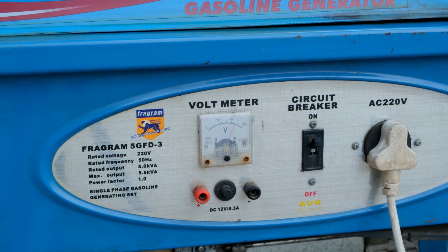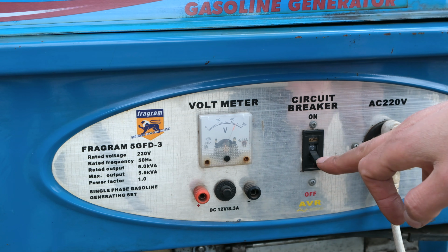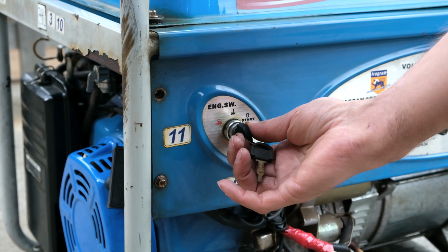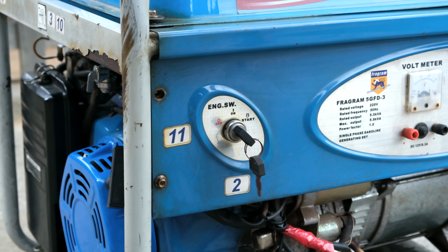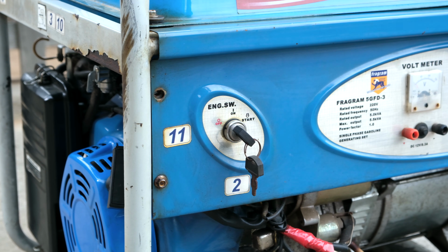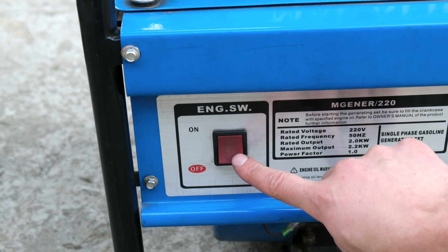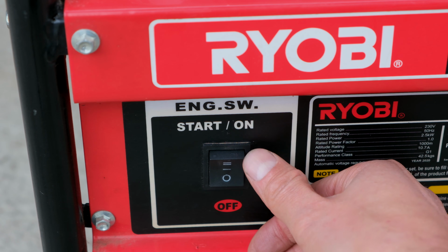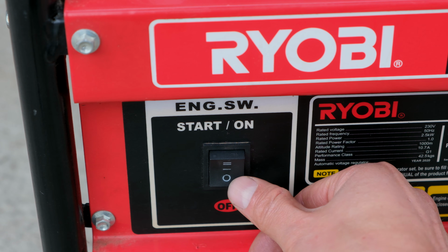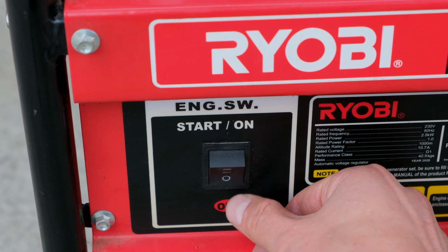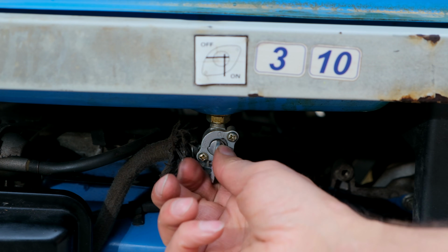To stop the generator, please do as follows. Switch off all your appliances. Put the circuit breaker into the off position or push it down. Turn off the generator by turning the key, or if it's a push button generator, switch the button to the off position. If the switch on the front of your generator has more than 2 positions, just make sure it's at the 0 position or the off position. You can now close the fuel valve.